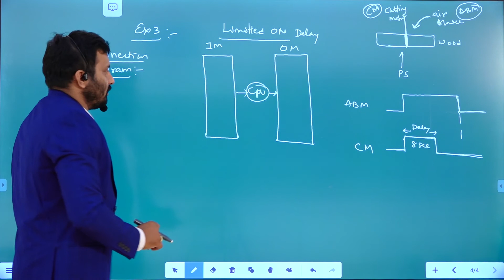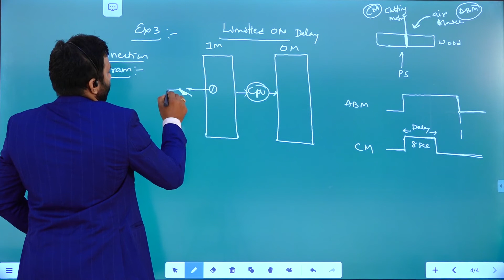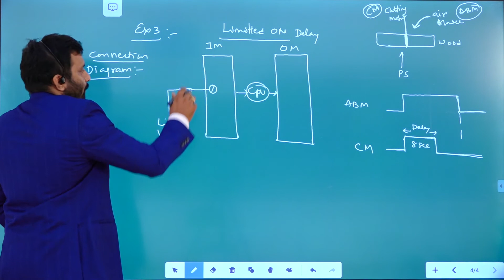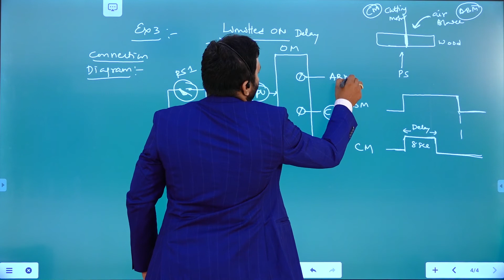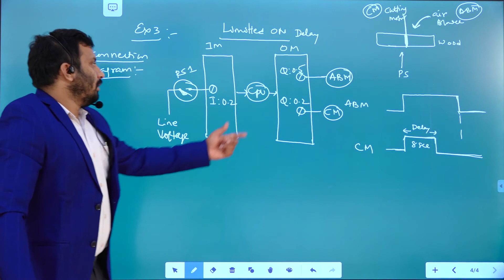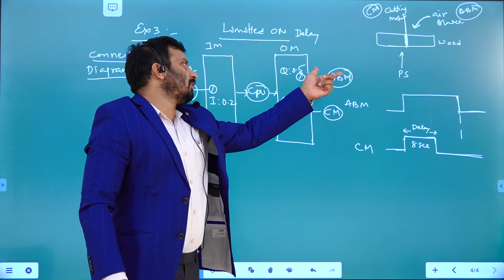Both are going to have power supply terminals, and the remaining terminals we are going to use. To this terminal I connected a limit switch, the proximity switch. The line voltage is taken from the supply terminal of the input module. Two terminals are going to be connected to the outputs: one to the cutting motor, another to the air blowing motor. If you connect a switch to a terminal, it has some address, for example 0.2. Here also the two motors you connected have addresses, 0.2 and 0.5. To the third terminal you connected the cutting motor, and to the sixth terminal the air blow motor.